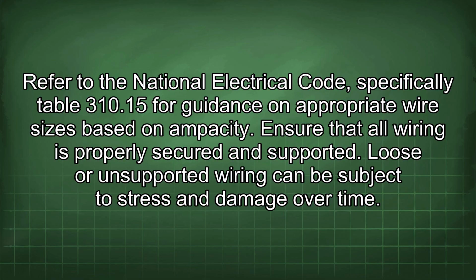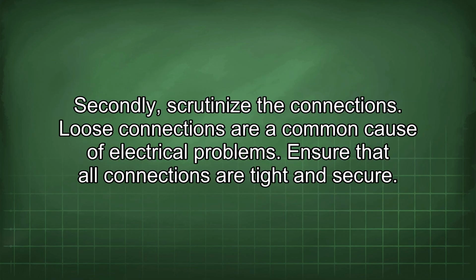Ensure that all wiring is properly secured and supported. Loose or unsupported wiring can be subject to stress and damage over time. Secondly, scrutinize the connections. Loose connections are a common cause of electrical problems. Ensure that all connections are tight and secure.